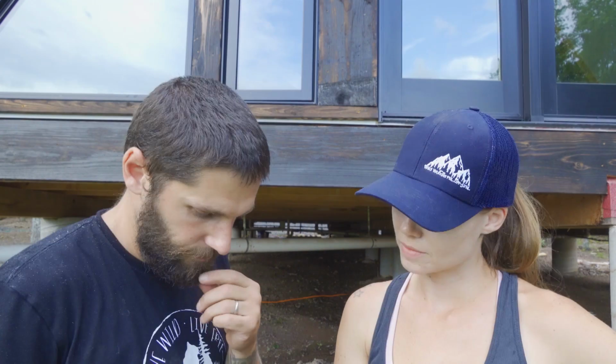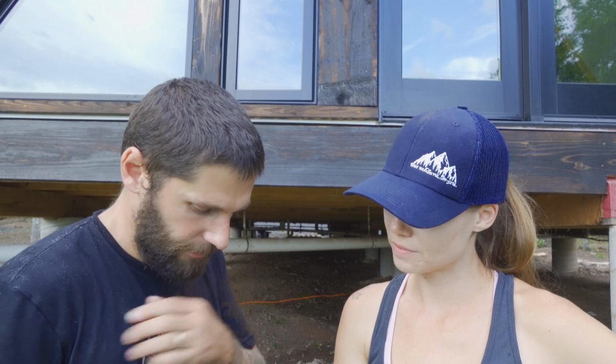So underneath, we're going to staple, what's it called? Bubble foil insulation. Yeah, exactly. The bubble foil insulation, we're actually going to staple it to the 1x2s. So we're going to create a 2-inch air gap of hot air with the radiant pipe, and it's going to stay there. That's what's going to heat the floors and radiate through the entire house and heat the house. And once we get done with that bubble wrap, we go ahead and put our insulation in underneath, and then voila, it's done.